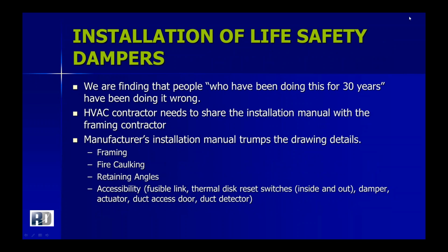So, installation of life safety dampers. The first line that we have indicated here is something that we hear so often. We talk to the framers, or we're talking to the sheet metal foreman or the guys doing the work, and oftentimes one of the first things coming out of their mouth is that, hey, we've installed fire smoke dampers, fire dampers the same way for over 30 years. So after we have our little eye roll that they don't see, we have to politely indicate to them that, no, you have likely been installing those fire smoke dampers or fire dampers wrong for at least the last 25, because manufacturers are continually changing and getting their devices recertified under UL processes, and those framing techniques change.